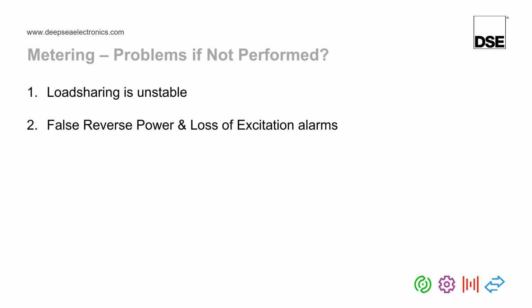We've had another question come in saying, what is the AVR max trim and how to solve it? I'm not sure what this is relating to, but I'm going to have a guess that maybe it is the alarm AVR trim limit. If you have ever seen the alarm AVR trim limit, then this suggests that actually your switch 2 value and switch 1 value have not been set up correctly. Effectively, what the AVR trim limit alarm means, if it has been enabled in your controller, is that the DeepSea module is trying to request the AVR to do more work, but unfortunately, it cannot. This might be because the AVR switch 1, switch 2 have not been set up correctly, so the DeepSea module does not have a good enough range of control, for example, plus or minus 10% of nominal voltage.